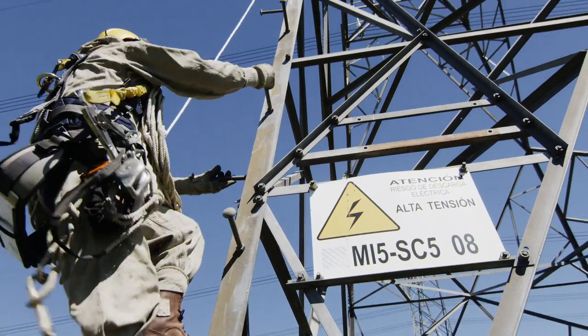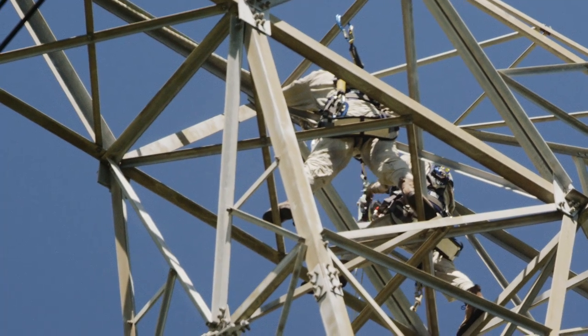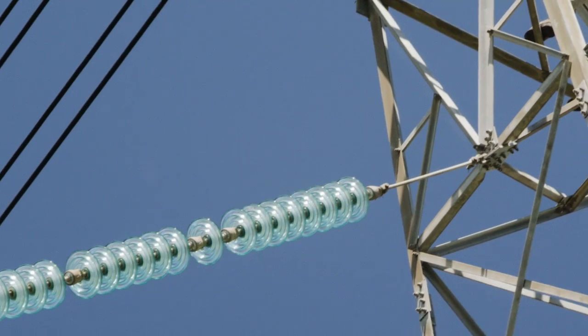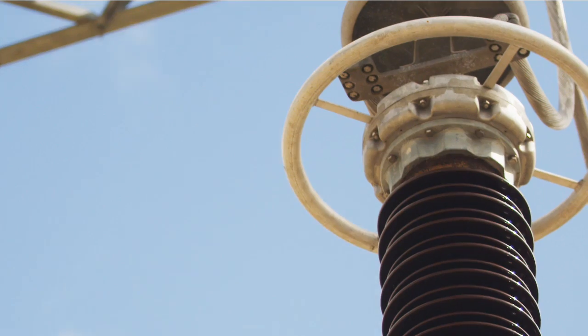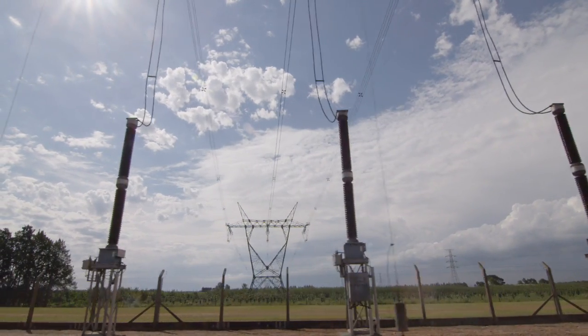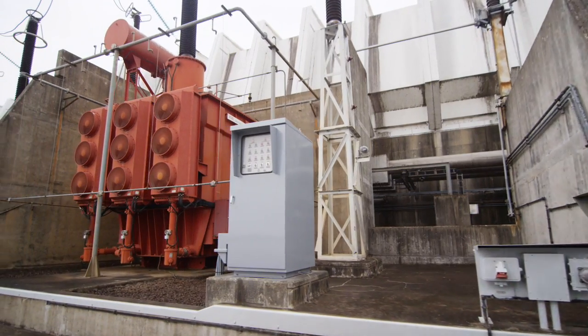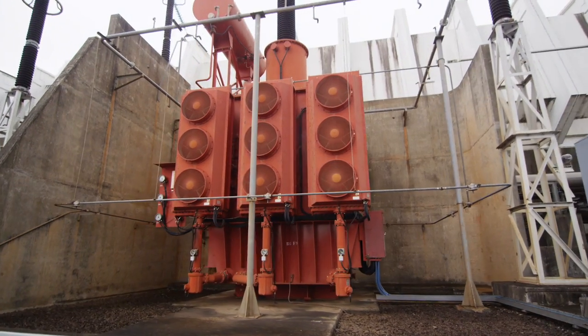This would now allow you, if you all of a sudden saw a flashover of an insulator, to actually pick that up with a traveling wave fault locator and repair that insulator before it caused the outage of the line. I like to talk about the need for speed. In this day and age, there's no reason to wait to clear a fault. Faster tripping is a tremendous opportunity from a point of view of voltage and angle stability, and from a point of view of safety — reducing fire risk and reducing damage to all kinds of electrical equipment.